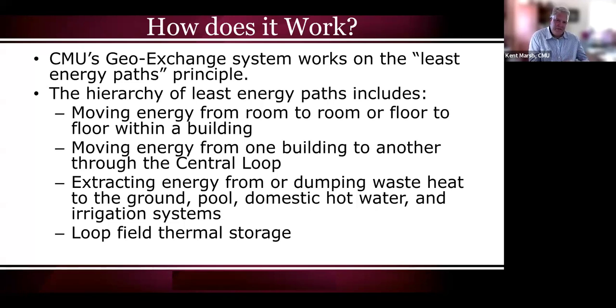Once that building loop gets too hot or too cold, we have the option to run that building loop water through a heat exchanger against our central loop. On one side is the building loop, on the other the central loop, and that heat exchanger lets us either extract heat from the central loop into the building, or dump waste heat from the building into the central loop.